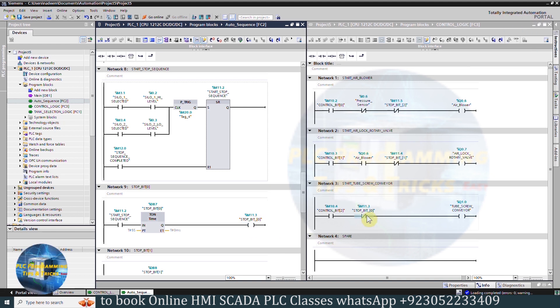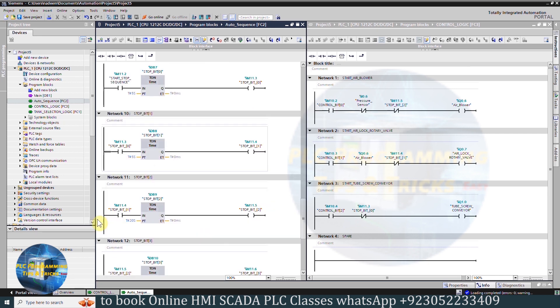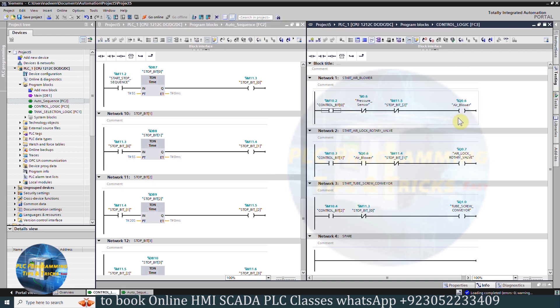The normal-close contact of stop bit 0 is used in Network 3, which will turn off the tube screw conveyor Q1.0. In Network 10, stop bit 0 turns on stop bit 1 after a 5-second delay. The normal-close contact of stop bit 1 opens and turns off the airlock Q0.7. Next, stop bit 1 turns on stop bit 2 after another 5-second delay, and the normal-close contact of stop bit 2 in Network 1 opens and turns off the air blower Q0.6.